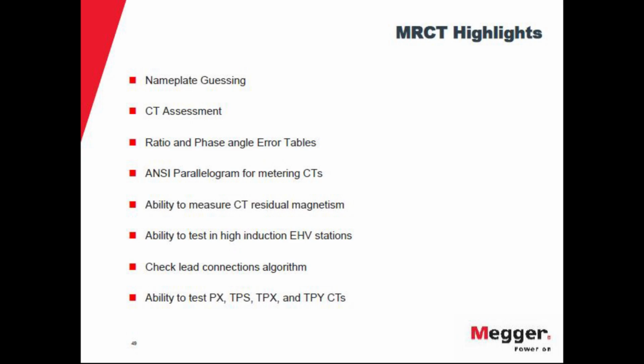You can get your ratio and phase angle error tables. You have the parallelogram for the metering CTs. So what I was mentioning about the ratio of metering CTs, that is compared to a parallelogram. Whatever result you get, the value is placed in a graph, and if it is outside the parallelogram, it means that it doesn't have the accuracy for the metering application. If it is inside the parallelogram, it will be valid for metering purposes.